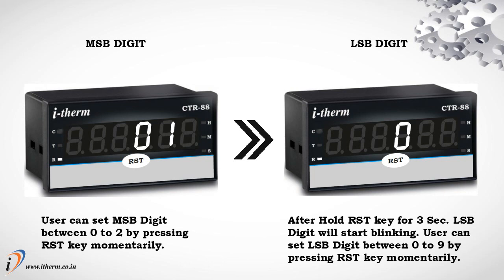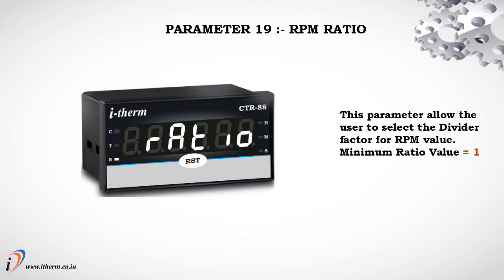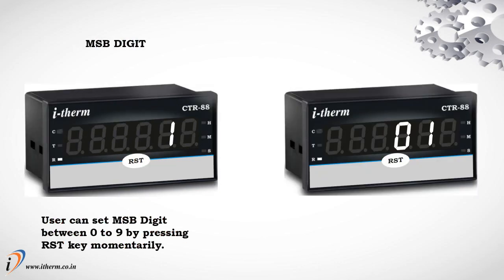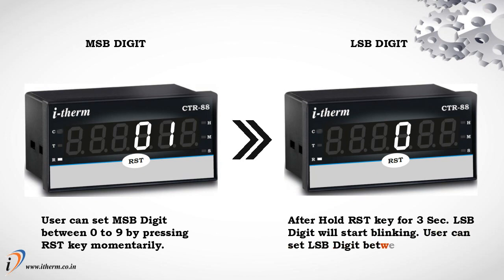Parameter 19: RPM ratio. This parameter allows the user to select the divider factor for the RPM value. Minimum ratio value equals 1; maximum ratio value equals 99. MSB digit: the user can set the MSB digit between 0 to 9 by pressing the reset key momentarily. LSB digit: after holding the reset key for 3 seconds, the LSB digit will start blinking; the user can set the LSB digit between 0 to 9 by pressing the reset key momentarily. This is the last parameter of the configuration list. Press and hold the reset key for 3 seconds to enter run mode.